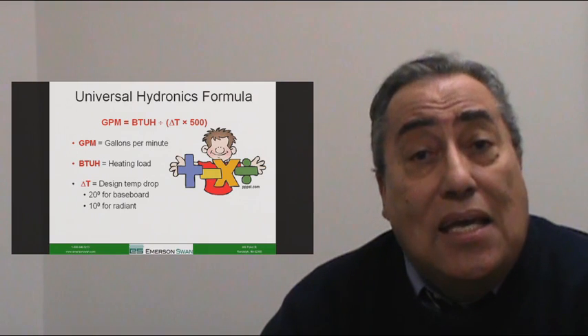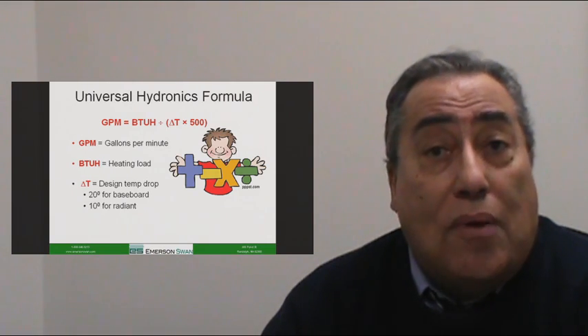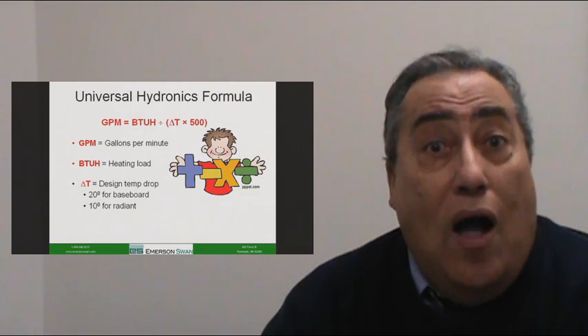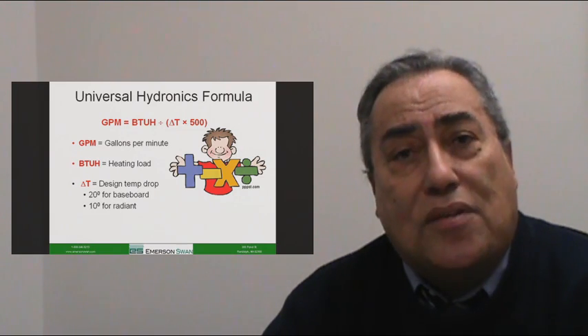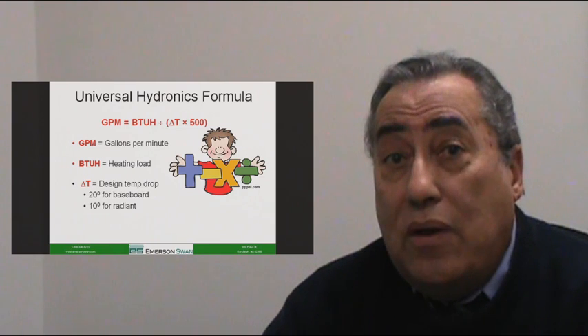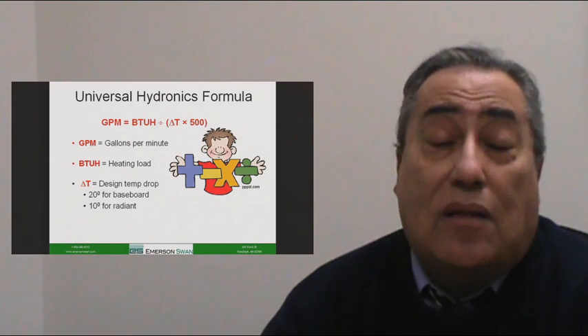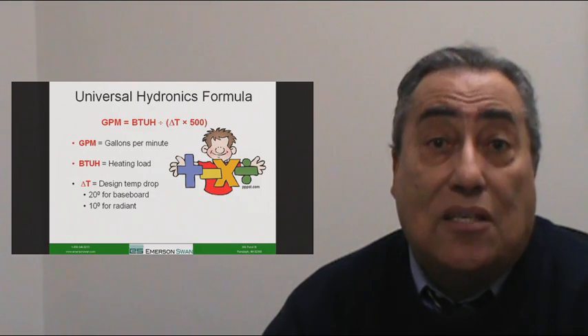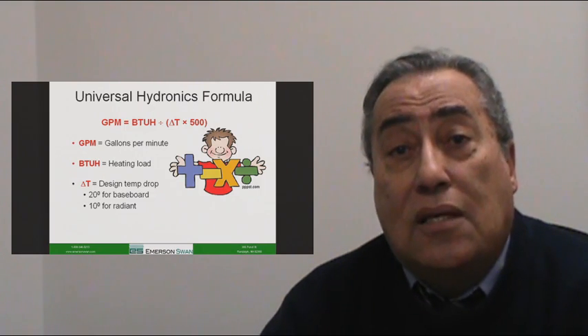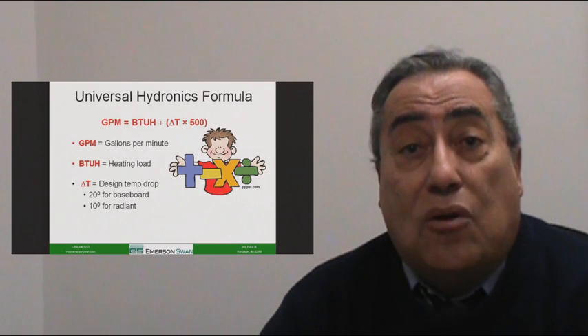The Delta T is the design temperature drop across that system on the coldest day of the year. In a baseboard series loop system, we design around a 20-degree Delta T. Assuming the water temperature goes out at 180 degrees, it would come back at 160 degrees. This is the traditional design for standard baseboard.